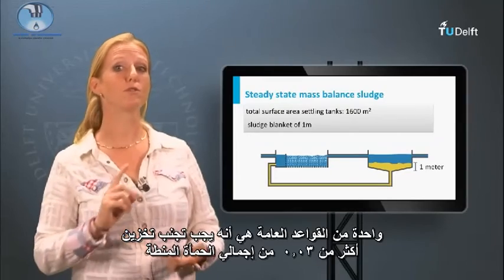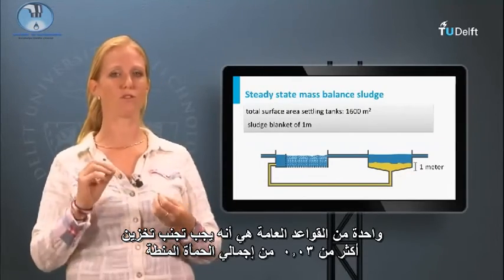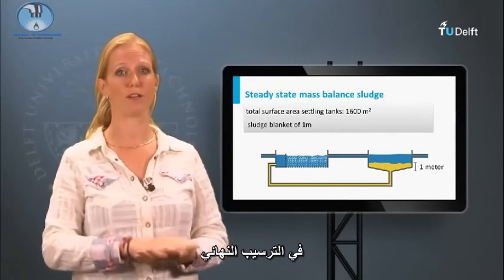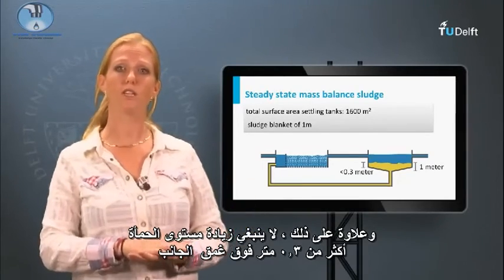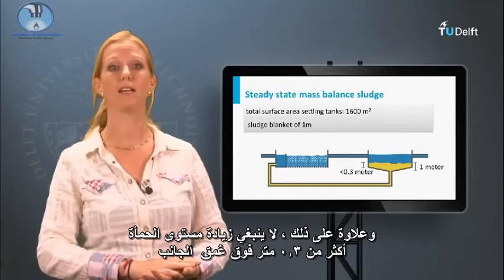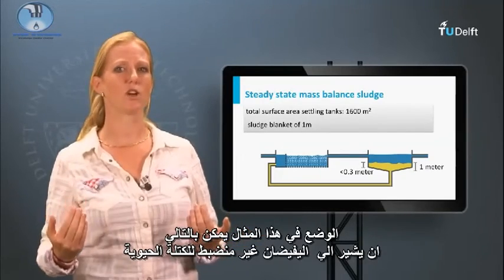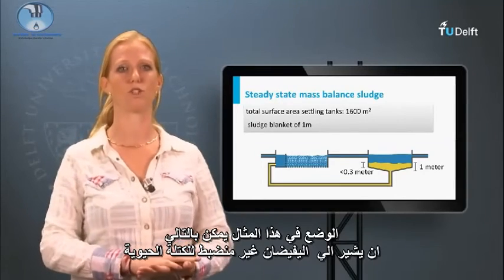One of the rules of thumb is that the storage of more than 30 percent of the total amount of activated sludge in the final clarifier should be avoided. Furthermore, the sludge level should not increase more than 0.3 meters above the side depth. The situation in this example could therefore indicate uncontrolled biomass washout.